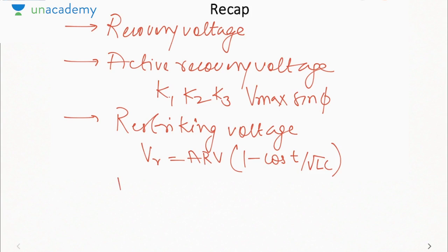Okay, and we determined RRRV, which was the rate of rise of restriking voltage, which was important in terms of recovery rate theory because we compare this rate with the rate of deionization or the rate of recombination. So these were the three voltages that we defined in conjunction with the circuit breaker arc phenomena.